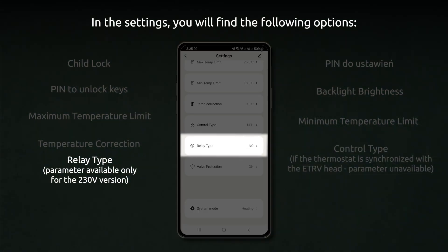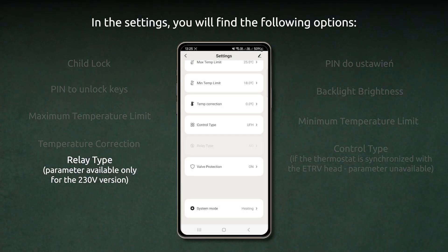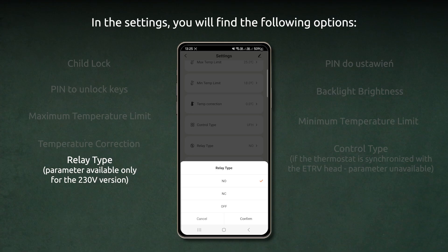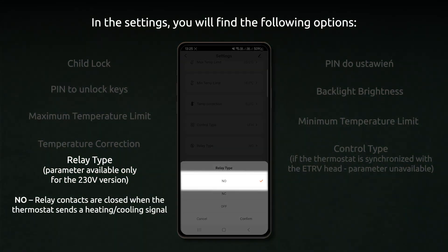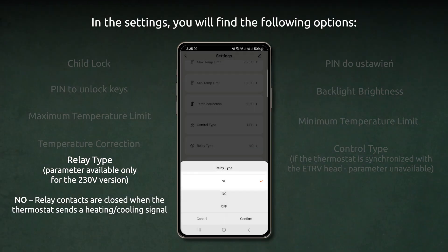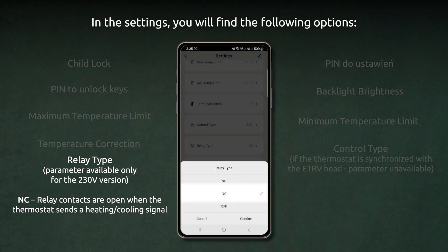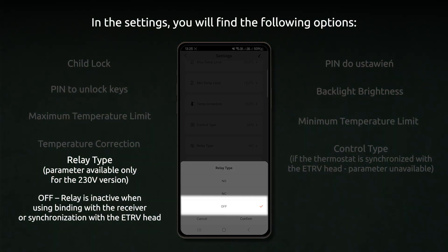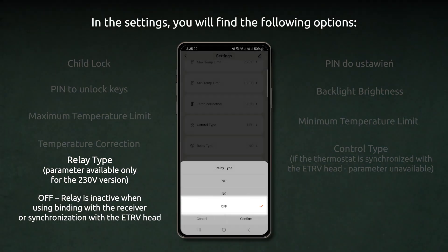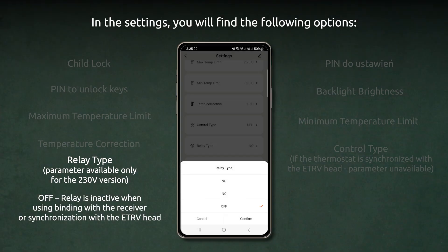Relay type. This parameter is available only for the 230V version. NO: relay contacts are closed when the thermostat sends a heating or cooling signal. NC: relay contacts are open when the thermostat sends a heating or cooling signal. Off: relay is inactive when using binding with the receiver or synchronization with the ETRV head.